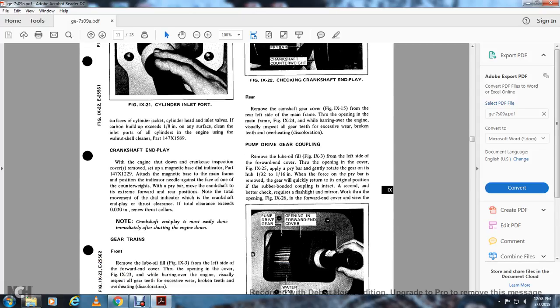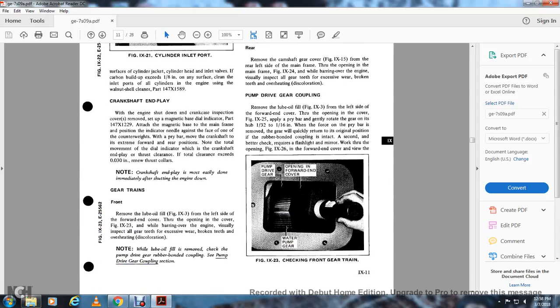Gear trains — front: Remove the lube oil fill (figure 9-3) on the left side of the forward end of the cover. This opening in the cover (figure 9-23) allows visual inspection of all gears for excessive wear, broken teeth, and overheating/discoloration.